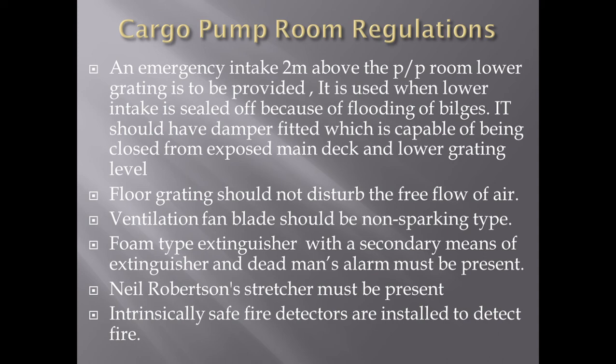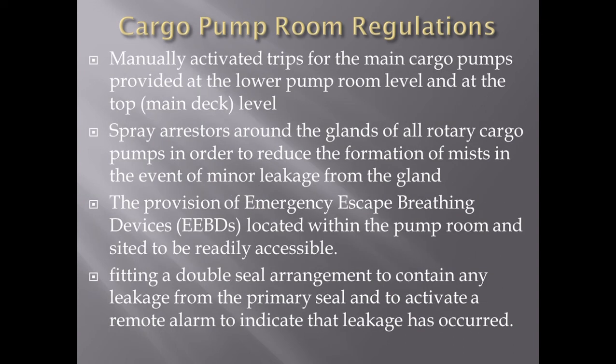All fire detectors used inside the pump room must be intrinsically safe, so there is no chance of fire. Manually activated trips for the main cargo pump must be provided at the lower pump room level and at the top main deck — essentially an emergency stop. In case of an emergency, we can stop the pump from the main deck or from the cargo pump room itself.